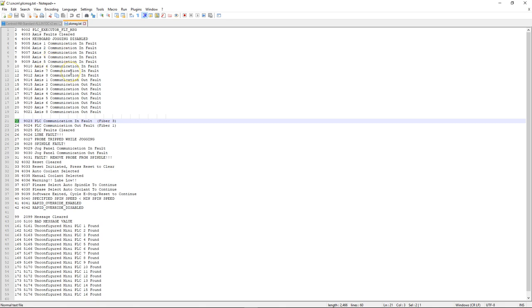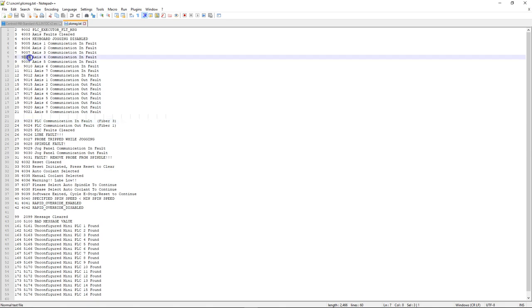In the message file, the column displaying the actual message always starts with a four-digit number that includes the error code. This serves two purposes: it gives a visual representation so anyone assisting the operator knows that a four-digit number means the PLC program is setting that message. A three-digit or 1000-series number means the CNC software itself is setting it. Once they see the four-digit number, they know to go through the PLC program to find what condition is causing that message.